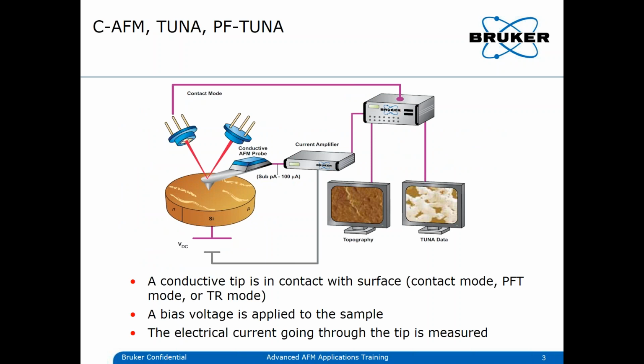So starting with conductive AFM, TUNA or Peak Force TUNA, all of them are using the same technique. You have a conductive tip which is in contact with the surface, like in contact mode, Peak Force TUNA mode, or in the torsion mode. And you have a bias voltage between the probe and the sample. And the electrical current going through the tip is then measured and amplified and sent to our controller. And you can get an image of your topography and your current data simultaneously, or also in the case of torsion TUNA, for instance, in interleave mode.